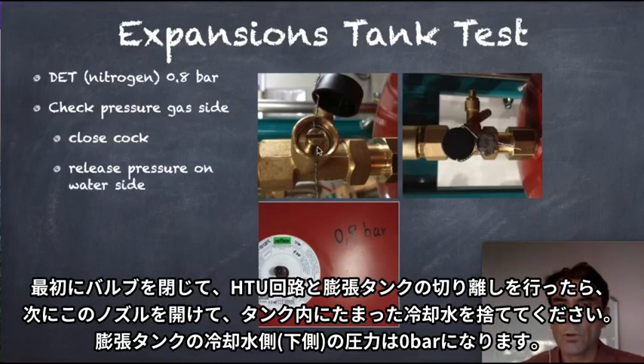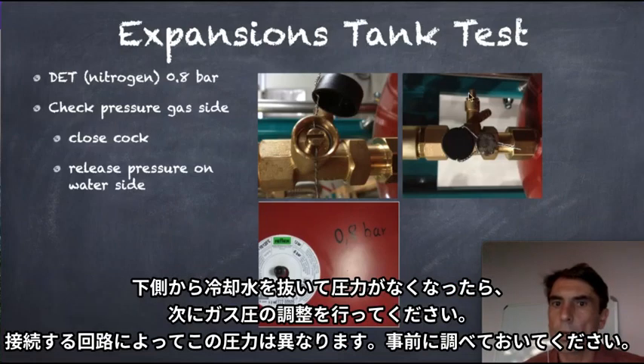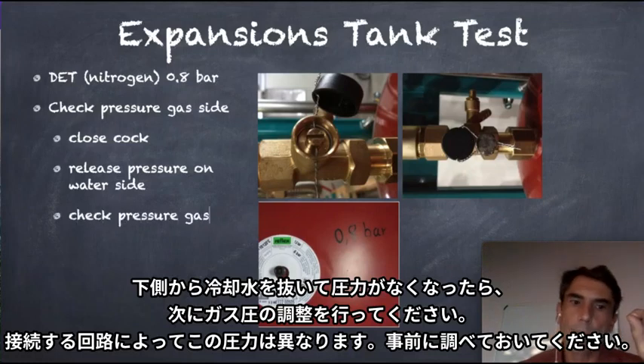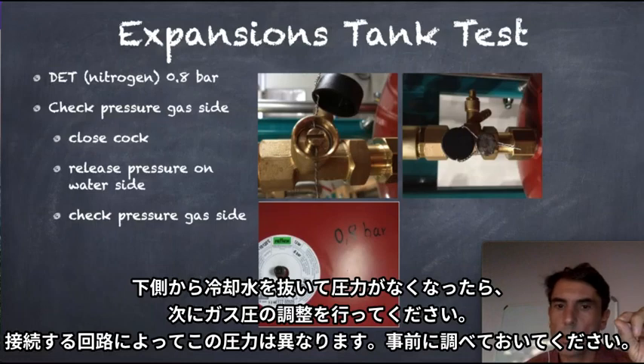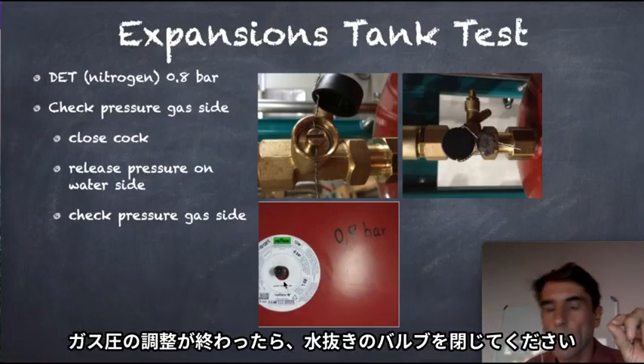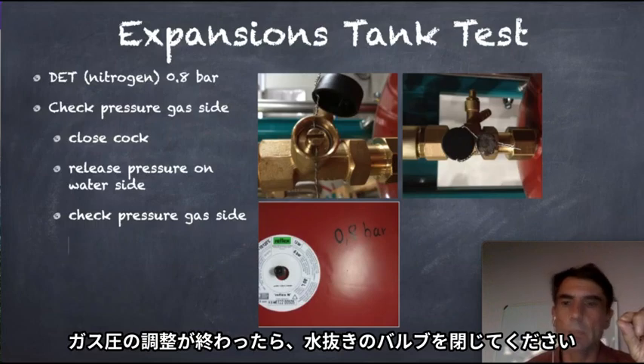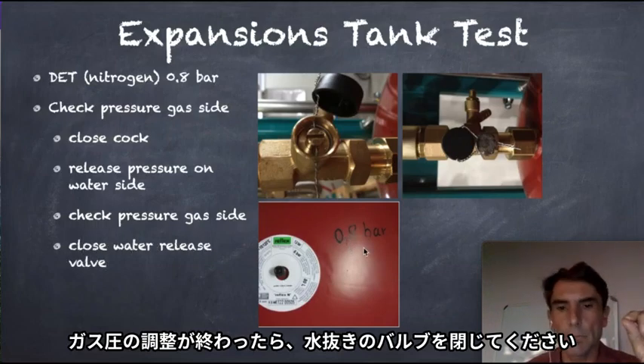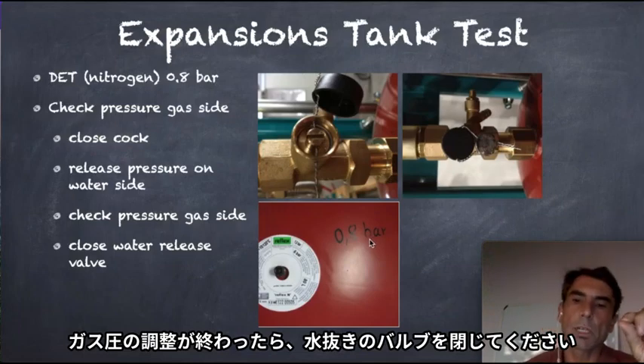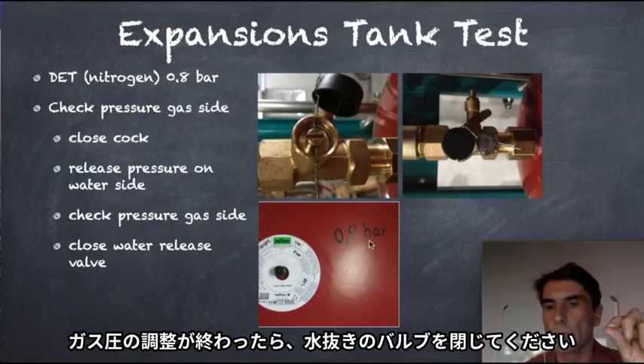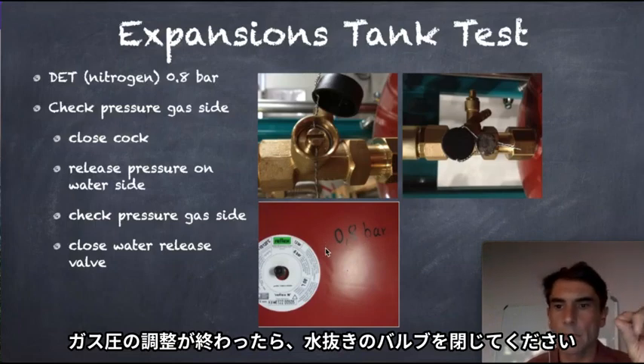So we close that valve first and then we release the pressure on the water side of the expansion tank. That can be done here. So we open that small valve and the water pressure will go out, and we will not have any water pressure on the water side of the expansion tank anymore. Now we can check the gas pressure, and we can either release it if the pressure is too high, or we can fill up the pressure. The target here, for example, is 0.8 bar. On the expansion tank of the charge air cooler safety module it is 1.5 bar, and so on. Different pressures.